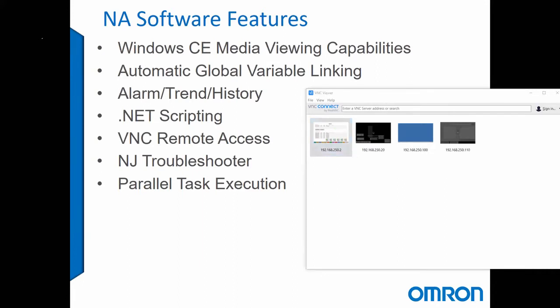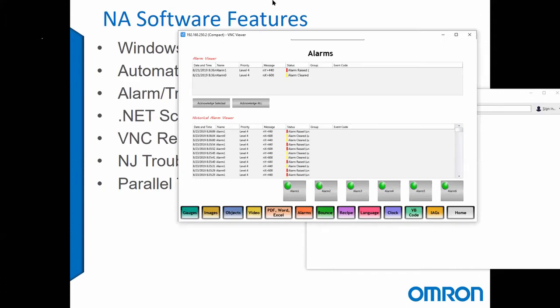I have a password set up on it. You can set this up as view only or view and control. Mine is view and control. And this is the HMI I have in front of me. It essentially mirrors the screen. So if I change a page on VNC, it's going to change on the HMI and vice versa. So it's not a thin client, it's a mirror of the screen.